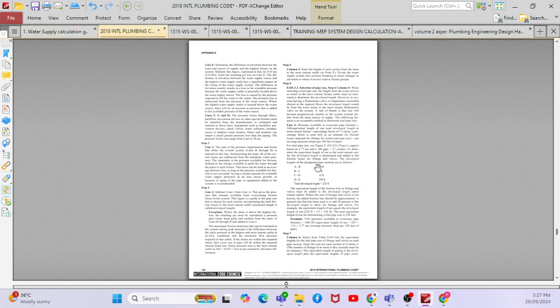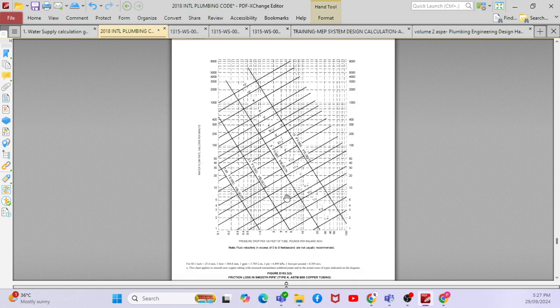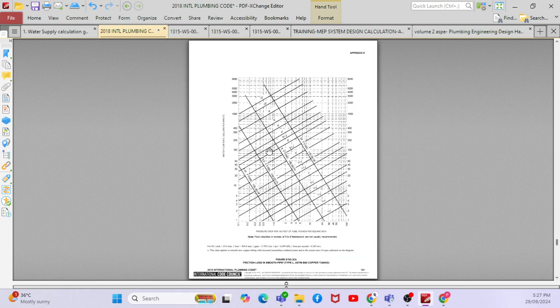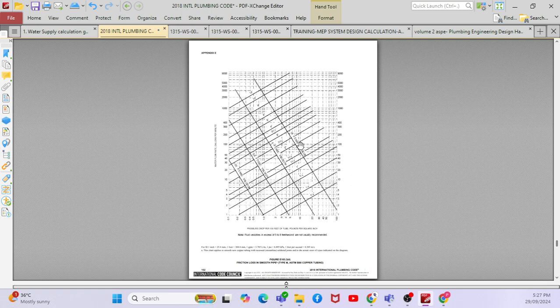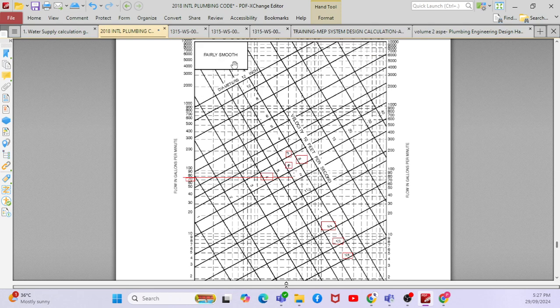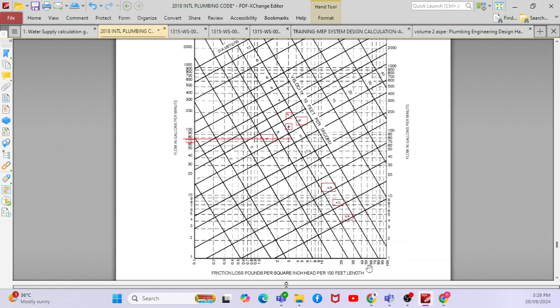If you go to the IPC standard, there is a chart for each pipe type — for example, copper pipe. Assume we are using a fairly smooth pipe. The recommended velocity is 4 to 8 feet per second. When you go to the flow rate and find the intersection with the velocity, you can calculate the pipe size. The chart shows the GPM line, pressure drop, velocity line, and pipe diameter. You can calculate flow rate, pressure drop, and pipe size all from this chart.